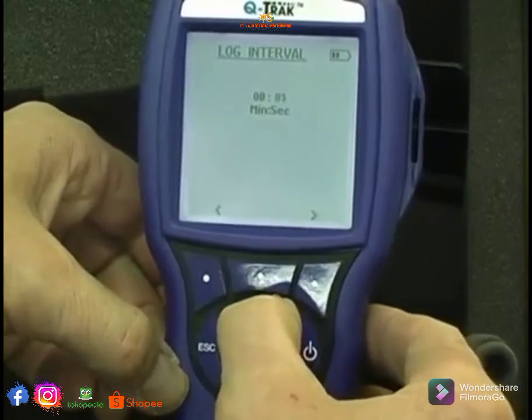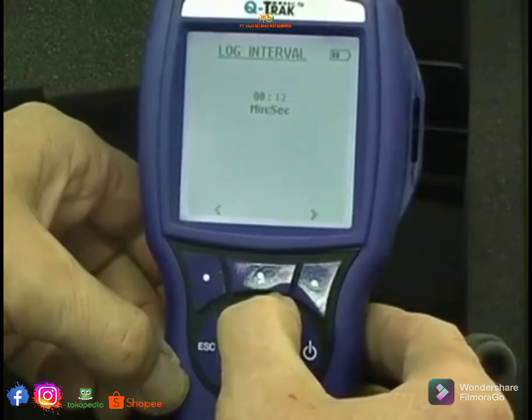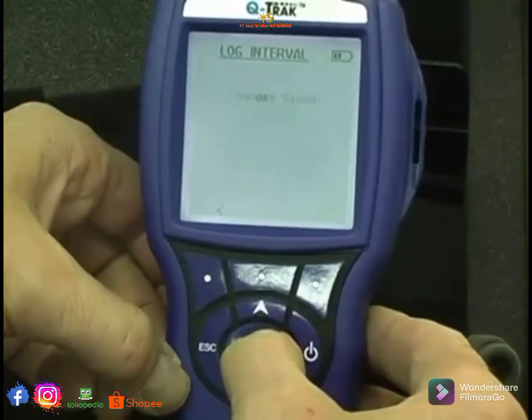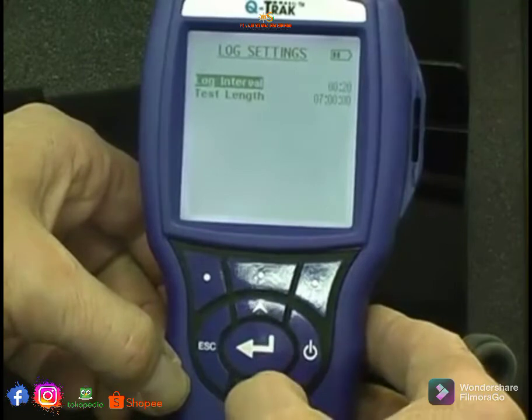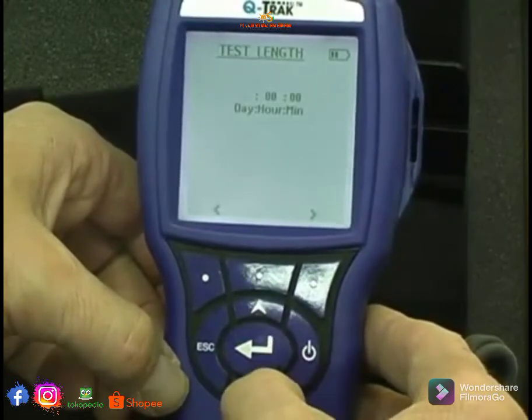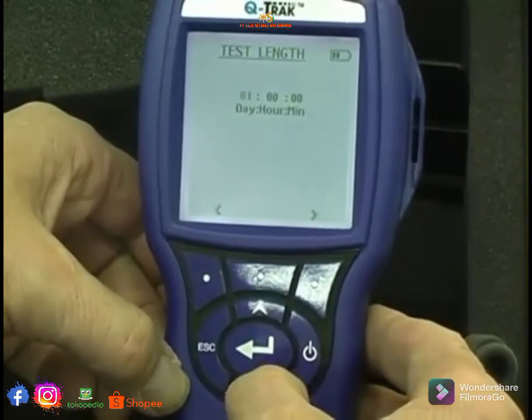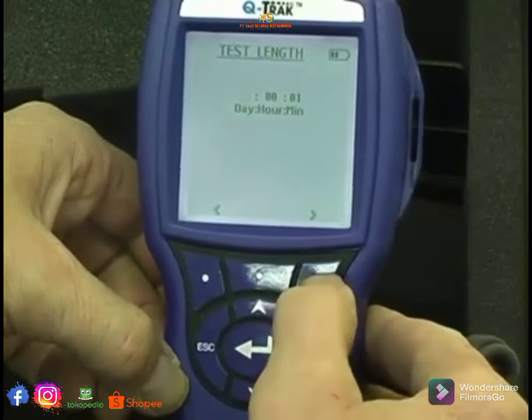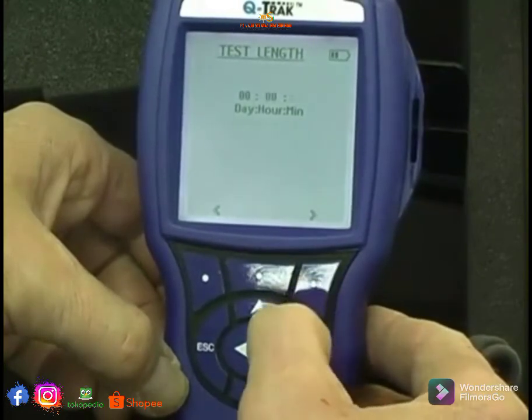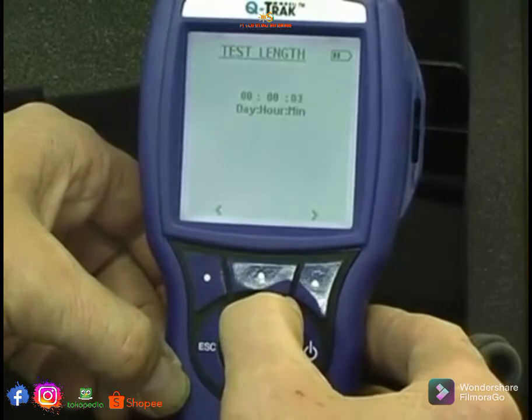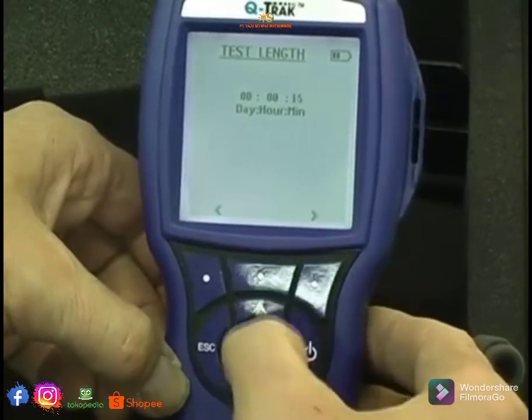Up to every 20 seconds will do. There we go. Enter, we save that, and the test length is going to be, instead of 7 days, I'm going to now set it down to 15 minutes. So there we are, and we can see what the readings look like after 15 minutes. Enter, we've saved the changes.